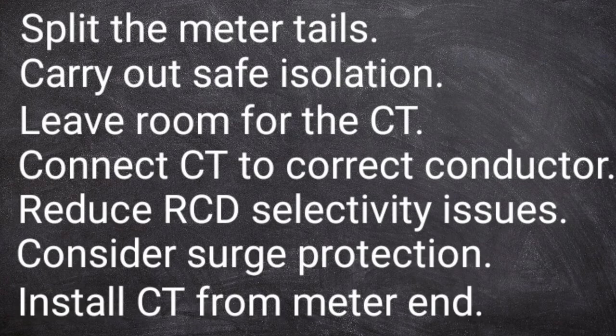You may also find yourself in a situation where you're installing multiple CTs and you might want to extend that with the same Cat5 cable, but use just one pair per CT, so one twisted pair from the Cat5 cable per CT, and that helps to avoid any crosstalk or miscommunication between the currents being measured in various conductors.